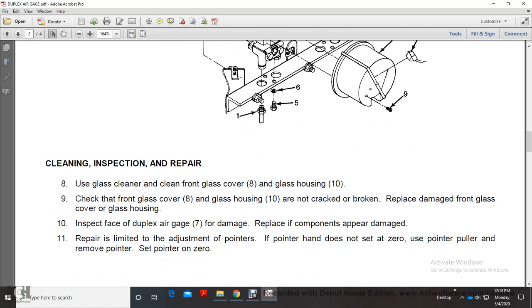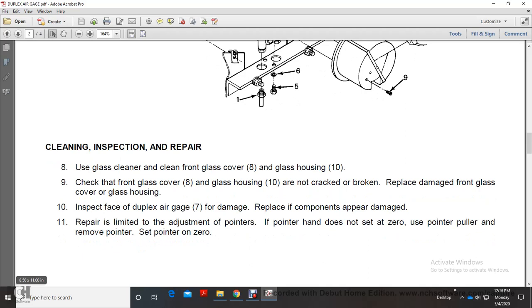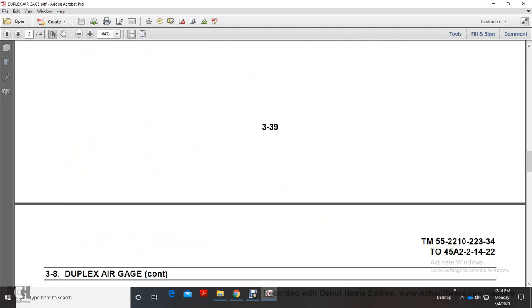Inspect the duplex air gauge for damage. Replace components that appear damaged. For limited adjustment of the pointer, if pointer is not at zero, use the pointer puller to remove the pointer.